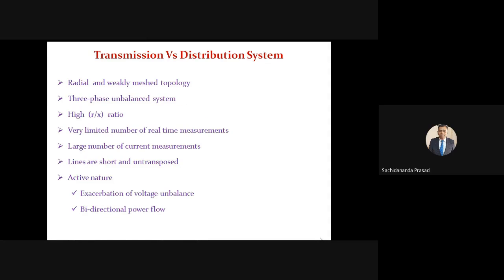As you know, there are some differences between the transmission and distribution system. Distribution system has some peculiar characteristics, which is why it becomes a more challenging task for power engineers, requiring huge research in this field to overcome all the issues in the distribution system. These peculiar characteristics include: your distribution system is radial in nature and weakly meshed, with few loops, it is an unbalanced system, and it has a high R/X ratio.